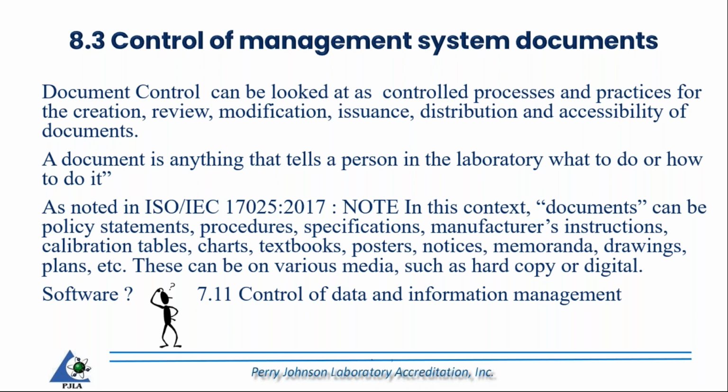What about software? We'll have to cover that during a separate webinar, but these requirements can be crosswalked over to that area as well. However, 17025 has it covered under Section 7.11, where it pinpoints control of data and information management.